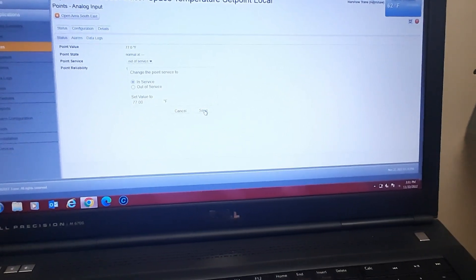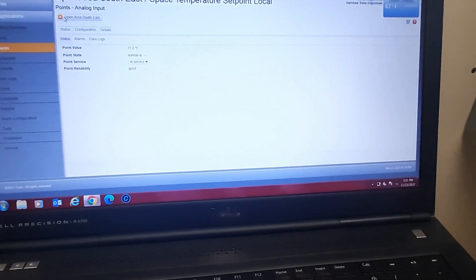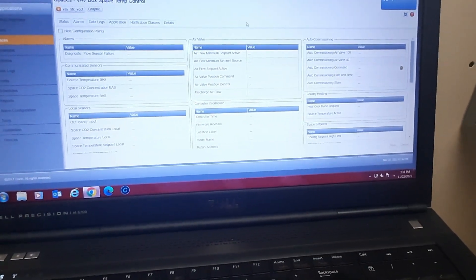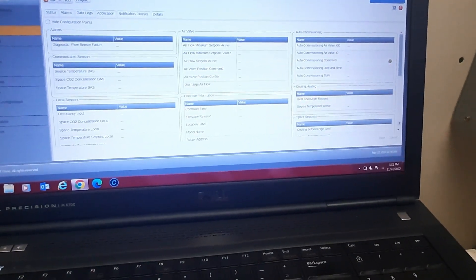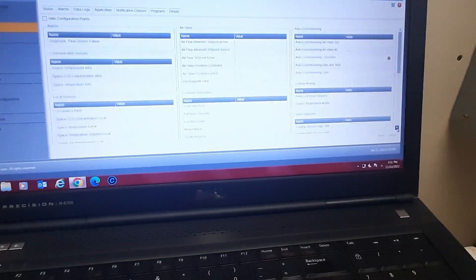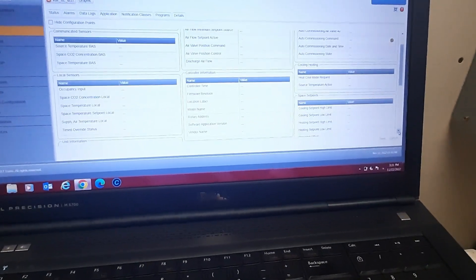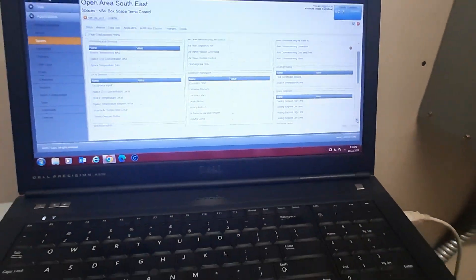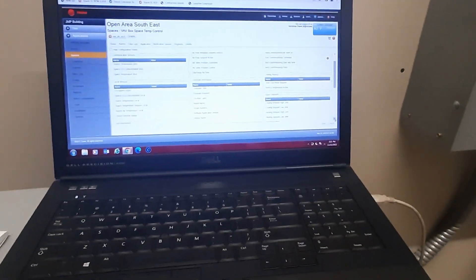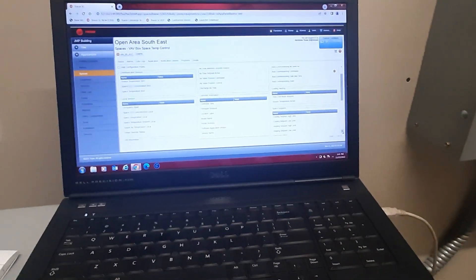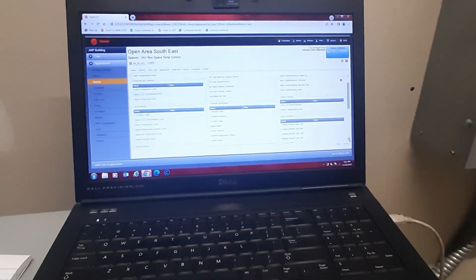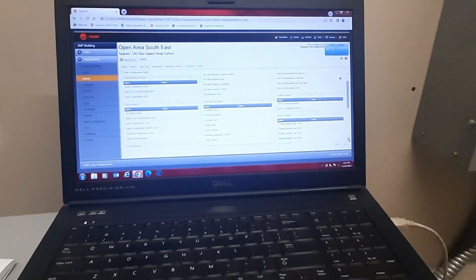In service, save, and that should go and take my actual local set point now. That was a big part of the reason why that space was warm or cold. The other space was doing okay but we adjusted it slightly, so we'll see how it does from there.